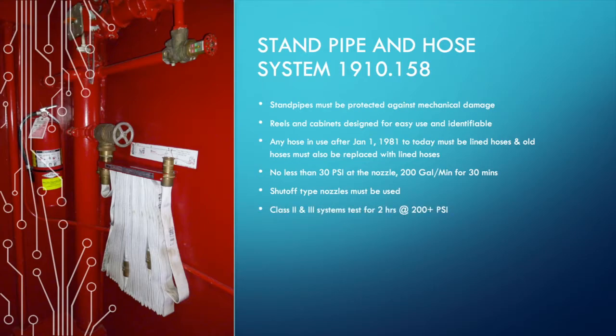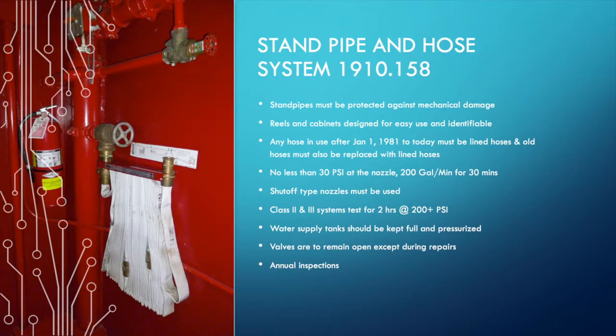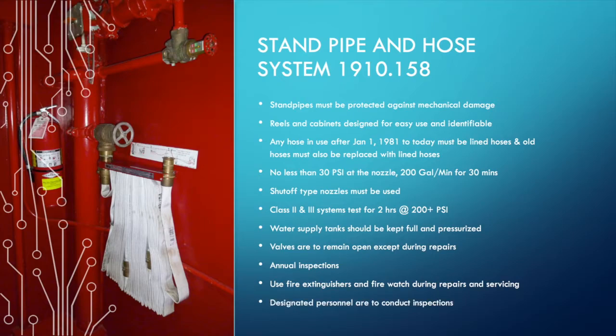Class 2 and 3 systems are tested for 2 hours at 200 plus psi. Water supply tanks should be kept full and pressurized. Valves are meant to remain open except during repairs. There must be annual inspections as well. Use fire extinguishers and fire watch during repairs and servicing. Designated personnel are to conduct inspections.